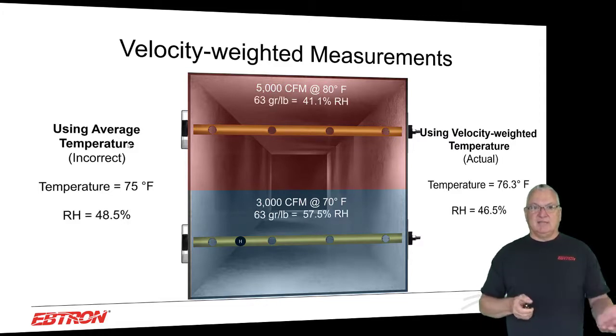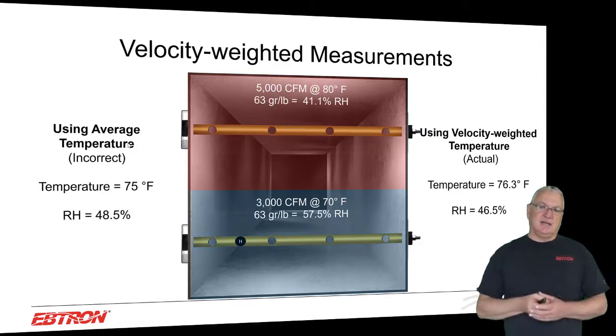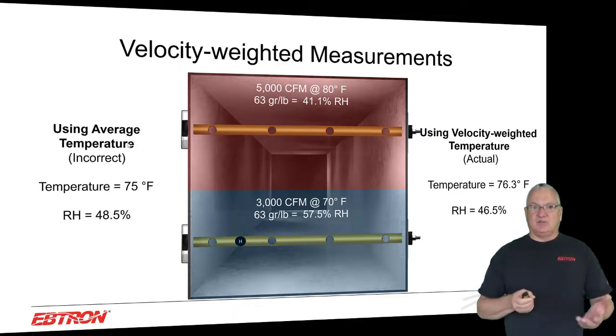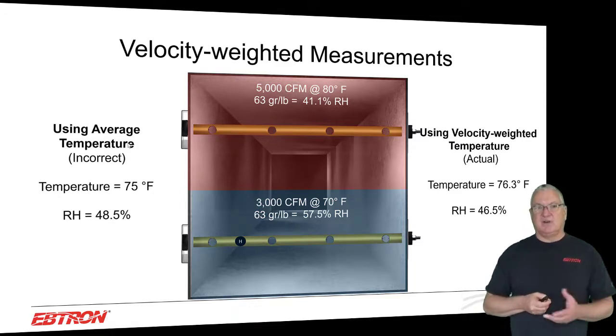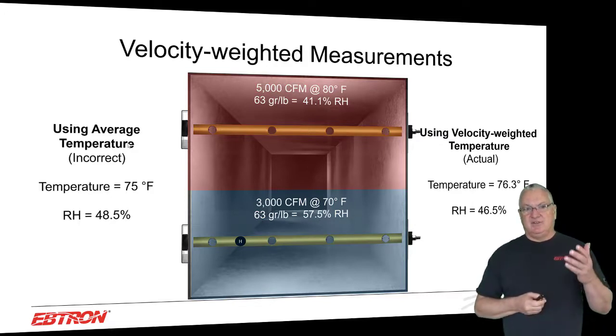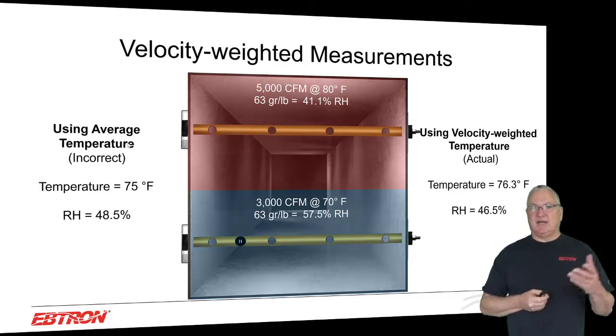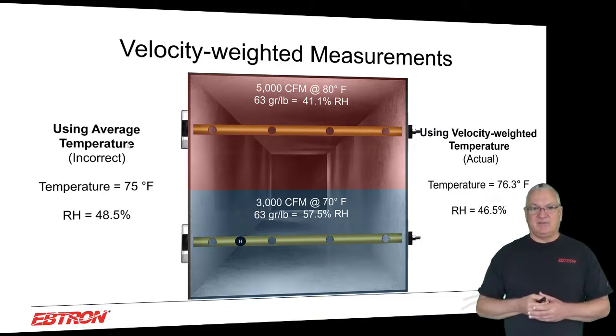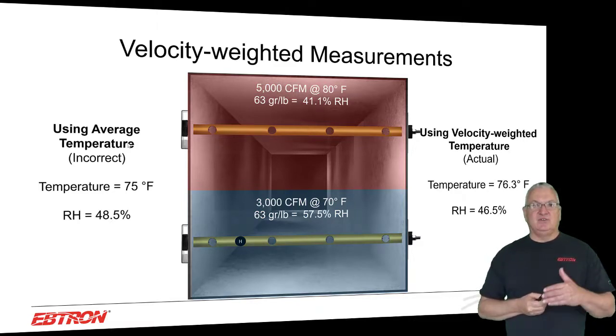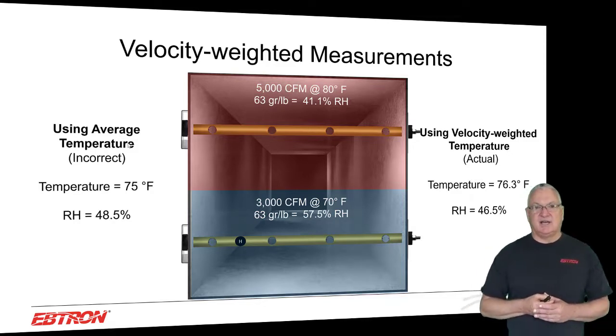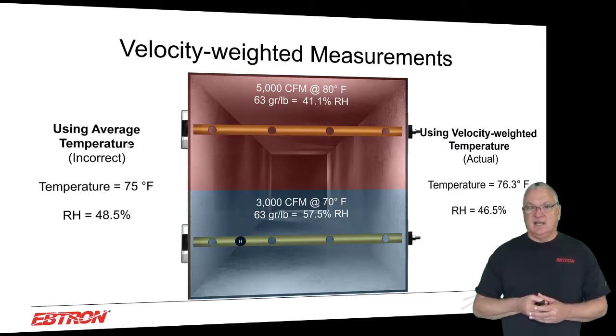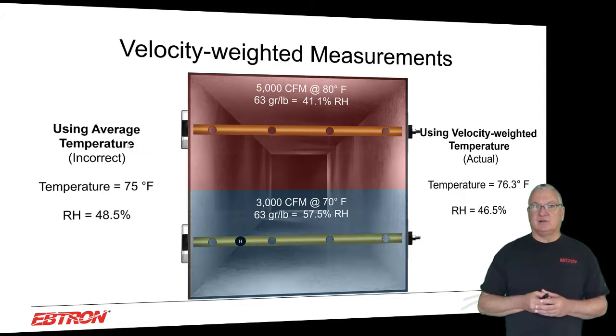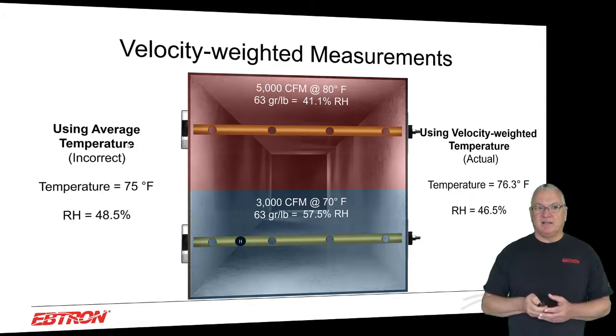When we take a look at the moisture side of it, let's assume that the actual grains per pound of moisture were constant throughout this profile. But again, you'd have two different relative humidities. On the top stream, you'd have 41.1%. The bottom, you'd have 57.5%. If you simply took the average, you'd have 48.5%. If you used the average temperature applied to a single humidity sensor, you'd have 48.5%, when the actual relative humidity is 46.5%. And that may be very important on some of your critical relative humidity applications.